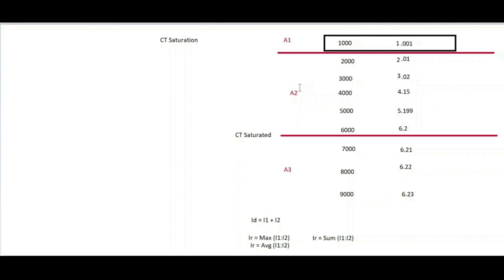In area 1 the error is different, in area 2 the error is different, in area 3 the error is different. So in 3 different ways it is working. To adapt it to these 3 different types of errors, a formula called IR is introduced. And what was done is, ID and IR were plotted in a graph: IR, restraint current, and ID, differential current.